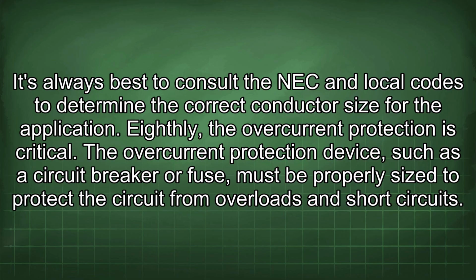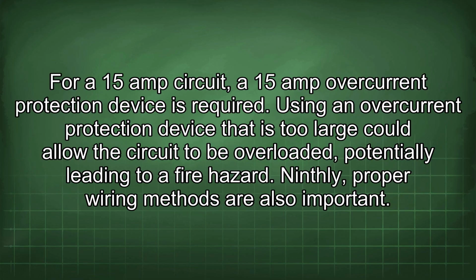Eighthly, the overcurrent protection is critical. The overcurrent protection device, such as the circuit breaker or fuse, must be properly sized to protect the circuit from overloads and short circuits. For a 15-amp circuit, a 15-amp overcurrent protection device is required. Using an overcurrent protection device that is too large could allow the circuit to be overloaded, potentially leading to a fire hazard. Ninthly, proper wiring methods are also important.